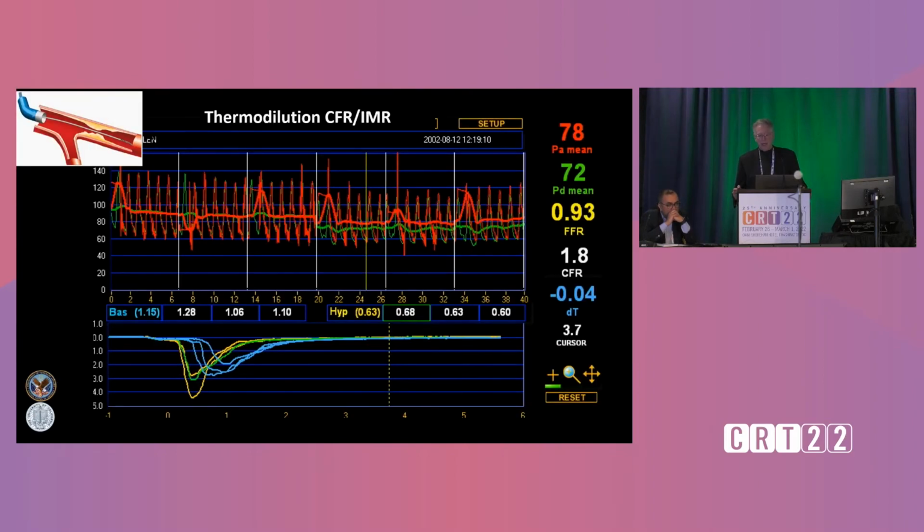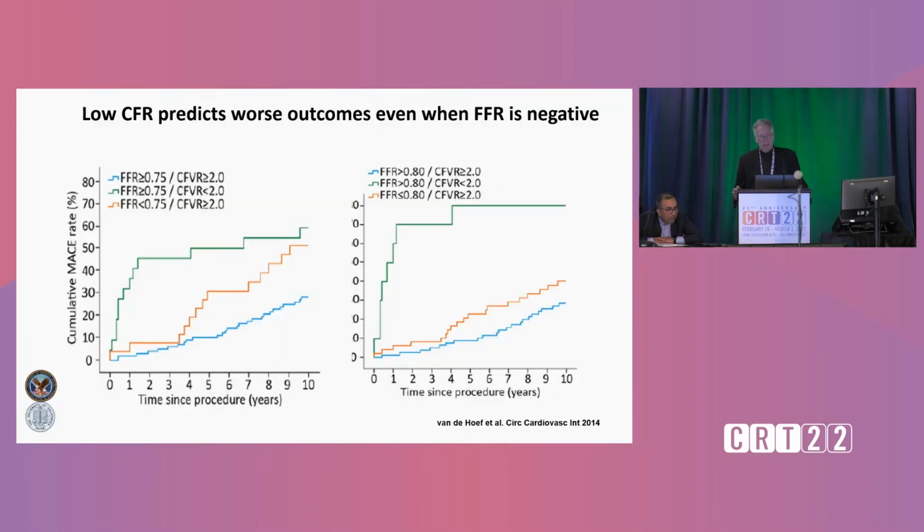Here it is again at a little higher scale. The technique involves having a device, usually input into the CoreFlow device, to give you IMR with its calculations. You have to inject 3 cc boluses by hand 3 times, accept the results, turn on the hyperemia, and inject again 3 times. So it's a little involved, but not completely difficult. And the information is going to be highly valuable to study the microcirculation, where we really need information that we haven't had before.